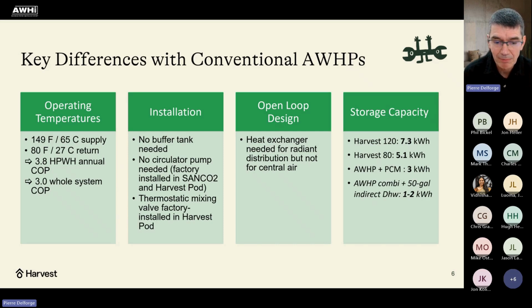Even PCM, phase change material products on the market today have a storage capacity around 3 kWh for the biggest residential models. Again, not enough to shift significant space heating loads. So the key differentiator in the design is that we designed the system to have enough storage capacity to make a meaningful difference in terms of space heating load shifting.